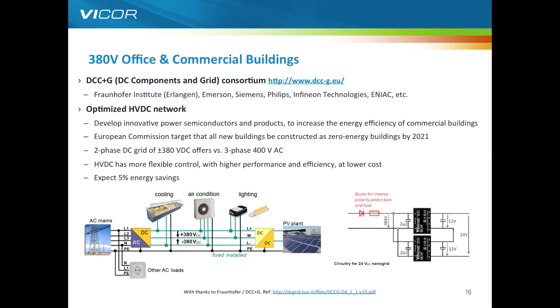On the right-hand side is an example of the Vicor bus converters. We have two units here with a transformation ratio of 1 divided by 32, so with 380 on the input we get 12 volts on the output. However, you can stack those outputs like Lego bricks and get 24 volts. That's used as a microgrid within rooms to provide power for laptops, LED lights, and similar things. This will be the second of the seminars in the new year—high voltage DC in the building, the real infrastructure of it.